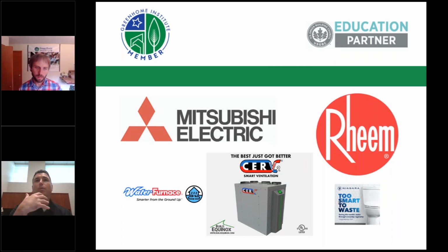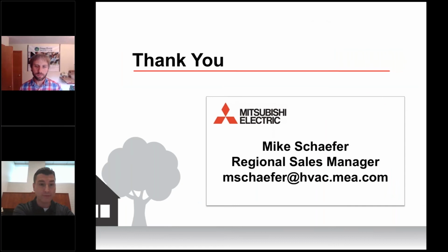Realistically, and I speak to applications that I've seen, it could be different in other parts of the country, but when electric baseboard is being utilized, it's being utilized as an emergency backup application. In that instance, a lot of times you're using the little controller or thermostat that comes on the baseboard heater. Turn it off, turn it on in an emergency scenario. Or if you're going to be gone, you turn it on and set it at a very low setting, whether that's 60 degrees or 55 degrees, whatever it is, just so that it will turn on in an emergency.